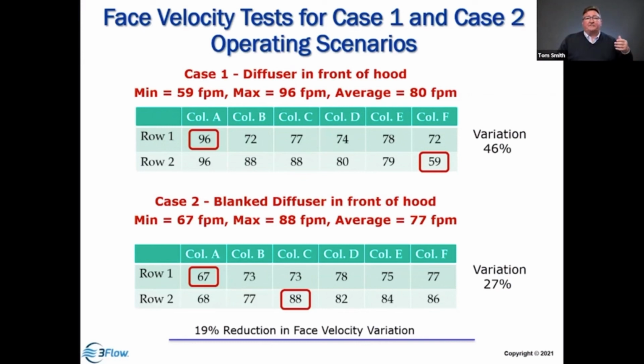Right? If it's too low or too high, those are issues we're working with. And sometimes we want to fix the hood or repair something. And if that work order is based on an inaccurate measurement, in other words, we made a mistake, we issued a work order, that's wasting time and effort. And it means that we're not going to have the same credibility as if we had done it properly. So using this technique creates the most consistent and repeatable method of measurement so that you can minimize the necessary work that's done to maintain it. There's going to be work for sure. We don't want to create excess work.